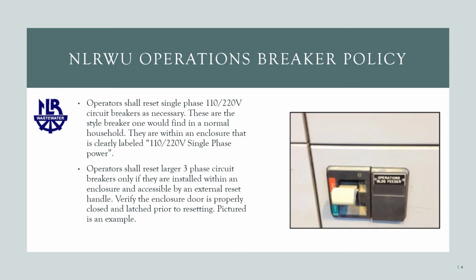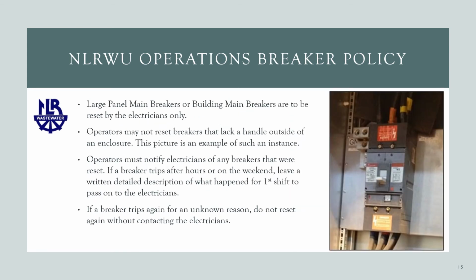Operators can reset larger three-phase circuit breakers as well, but only if they're installed within an enclosure and accessible via an external reset handle. Verify the enclosure door is properly closed and latched prior to resetting it. Here is a pictured example from the belt press room motor control center. Large panel main breakers or building main breakers are to be reset by the electricians only. Operators may not reset breakers that lack a handle outside of an enclosure. Pictured here is an example of such an instance.